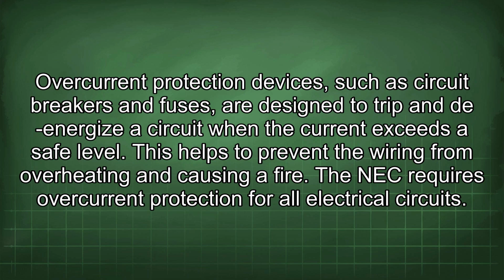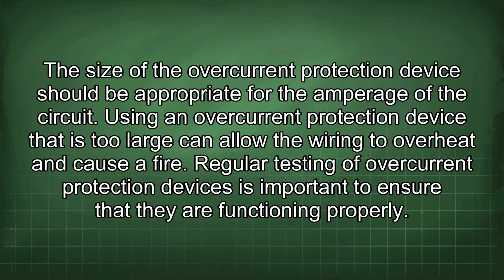The NEC requires overcurrent protection for all electrical circuits. The size of the overcurrent protection device should be appropriate for the amperage of the circuit. Using an overcurrent protection device that is too large can allow the wiring to overheat and cause a fire.